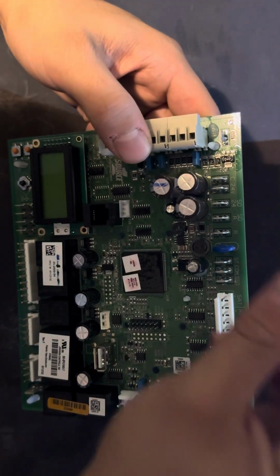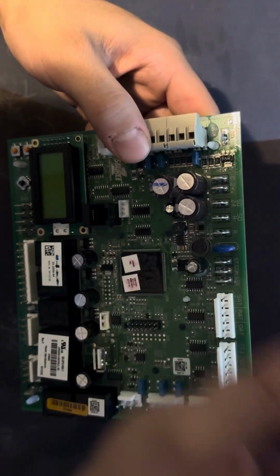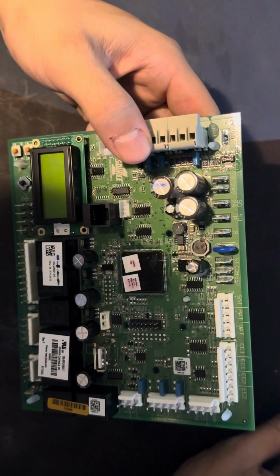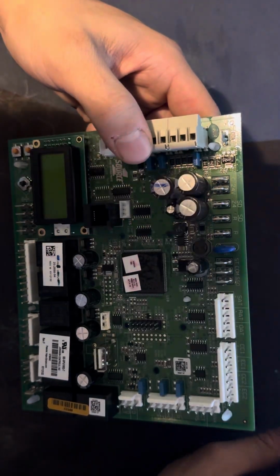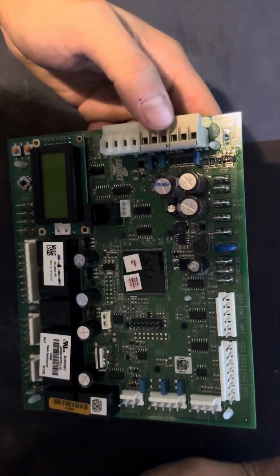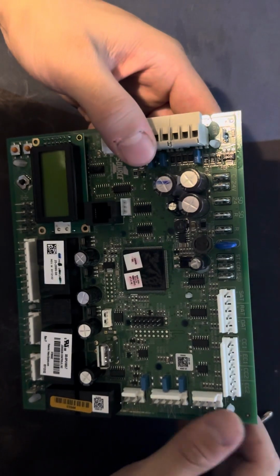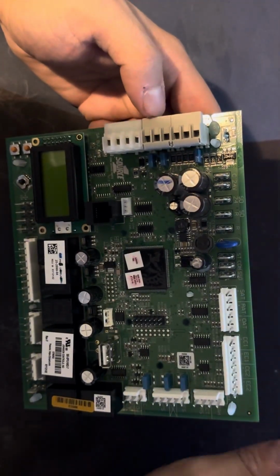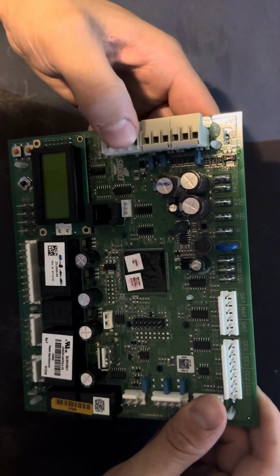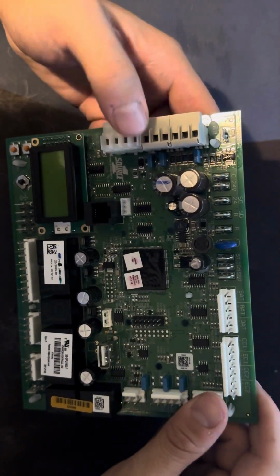All right. If you've exhausted all your options, you know, it's not corroded limits, it's not a contactor that's highly resistive and pulling too many amps, it's not the transformer, the only other thing I can think of is maybe a short in your thermostat wire, maybe your thermostat itself.